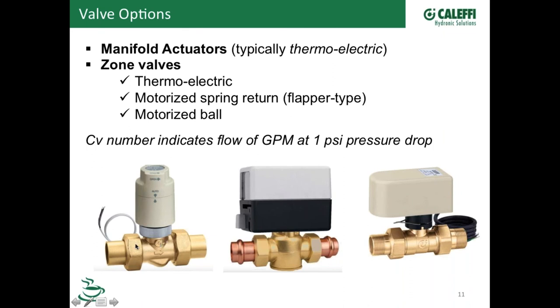This valve here has about a 4 Cv. Now the Cv number refers to how many gallons per minute you can flow through that valve with a one PSI pressure drop. So if we had a pressure gauge on both sides of this valve and we flow 4 gallons a minute through that, we'd have a 1 PSI drop. So not a super high flow valve, but certainly enough for small fin tube zones or obviously manifold actuators where you've got different loops on your manifold and you could put an actuator like that. There's a choice of different actuators that we offer, that's what we call our twist top there. Nice about that, you can manually lock it open so you can get flow going through and make your end switch for troubleshooting and stuff.